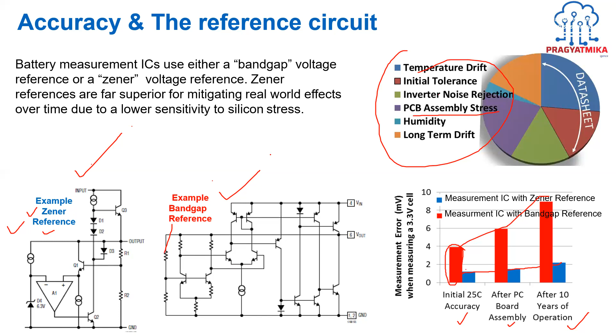And for the comparison, you can see the initial accuracies, and thereafter after board assembly or after 10 years of operation, in red we have the measurements done through the band gap method. So it is drifting much. There is a lot of drift in the measurements. Whatever figures you have planned in the initial years of production of your BMS front end will drift by almost 2.5 times. Whereas with the Zener reference method, there is a very small drift. It is not that there will be no drift, but there will be a very small shift in the accuracy that you will have. And nowadays almost all good BMS front-end chips have the Zener reference methods for your BMS applications.